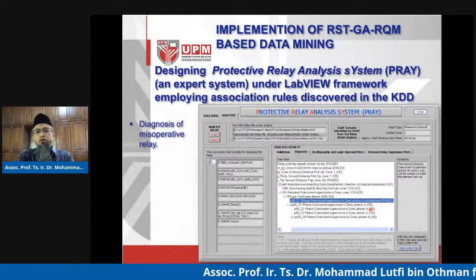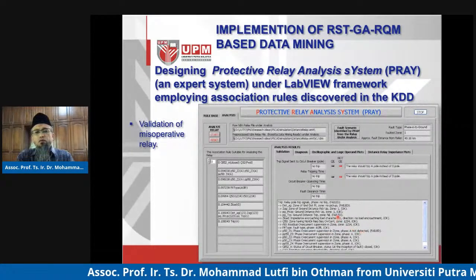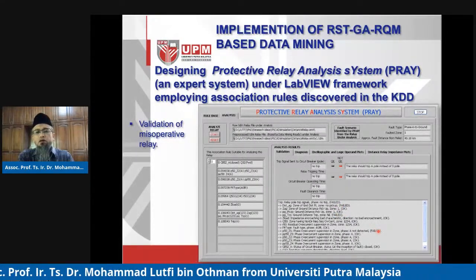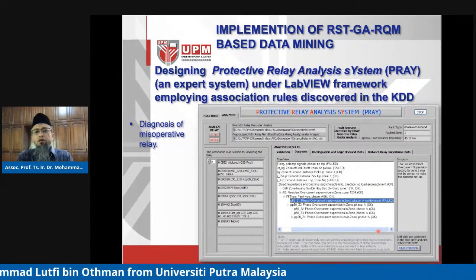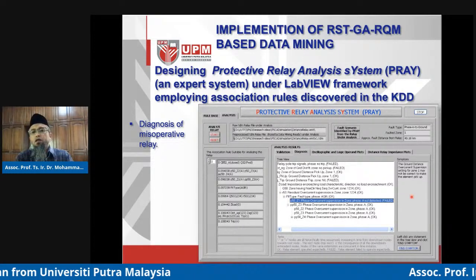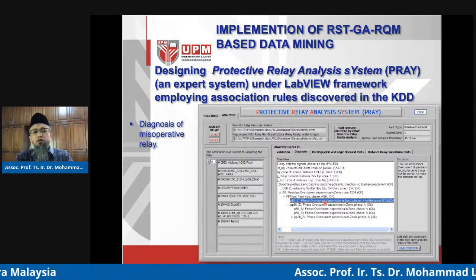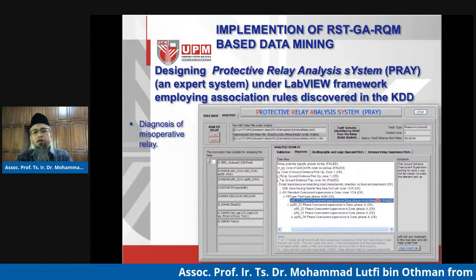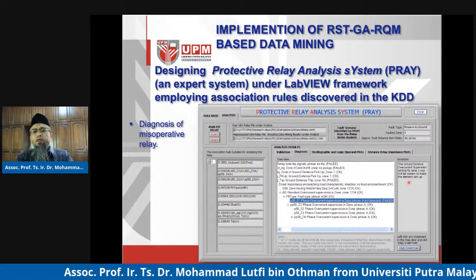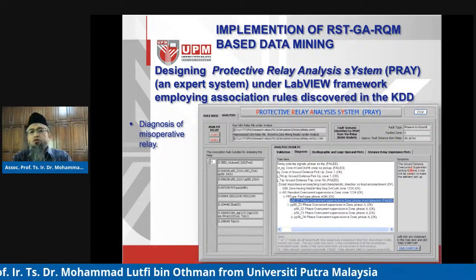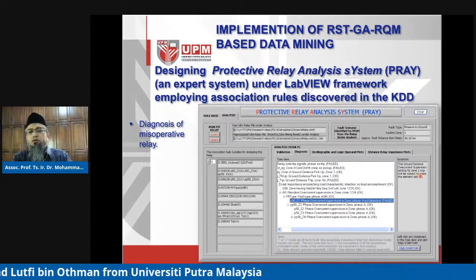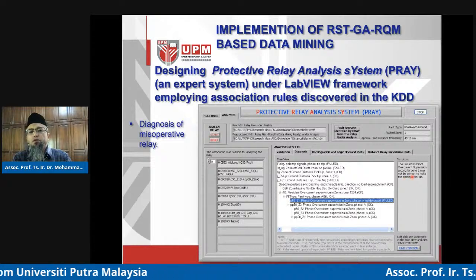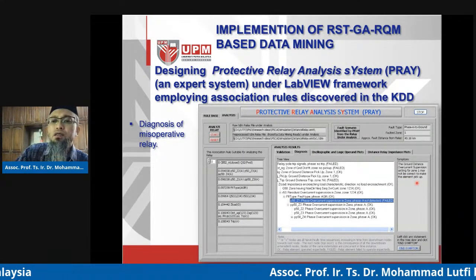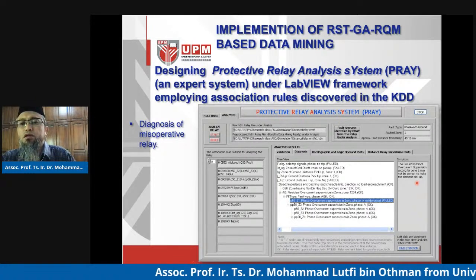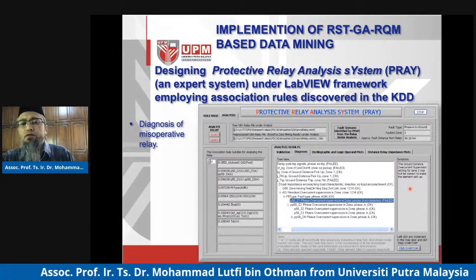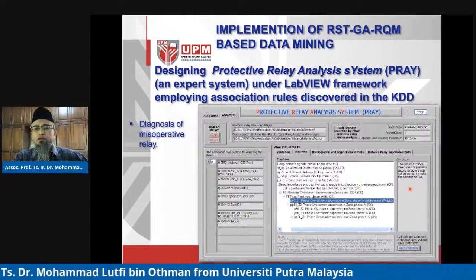What we do next is tick any one of the failed indications and see what has actually occurred, what kind of symptoms we can read from the situation. If we do that, we trip this overcurrent supervision unit, one of the tens of functional units within the relay. It is told that the ground distance overcurrent supervision setting of zone number 1 may not be correctly set. That's why it has given out the failure in the operation of the relay.